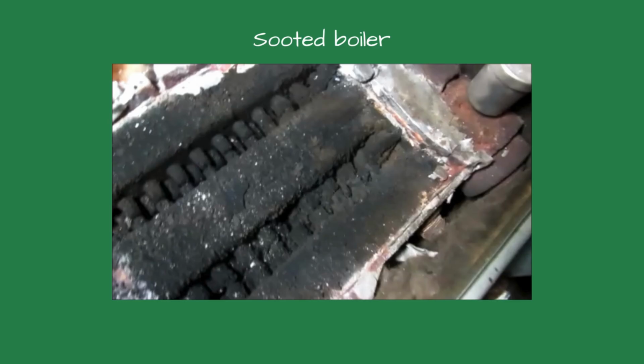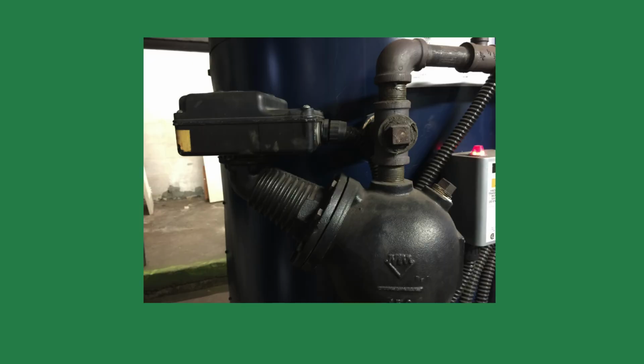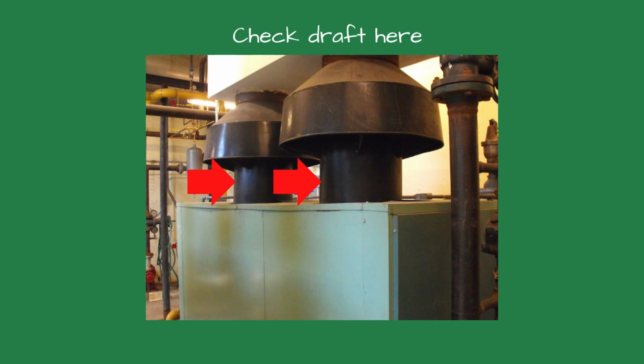Excess draft can also affect the operation of the boiler by creating erratic water levels, surging, and nuisance low water shutoffs. The boiler could be perfectly tuned with ideal combustion settings, but if your draft is off, you're burning cash. The sweet spot is a draft strong enough to clear the flue gases, but not so strong that it pulls the heat out with them.